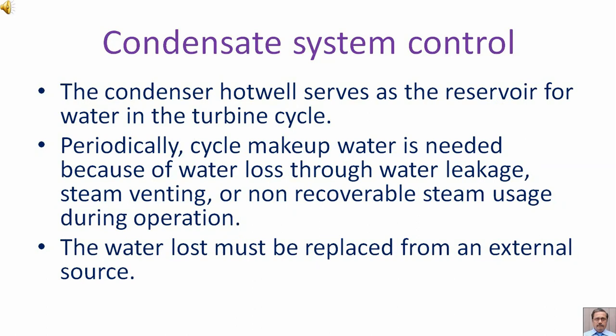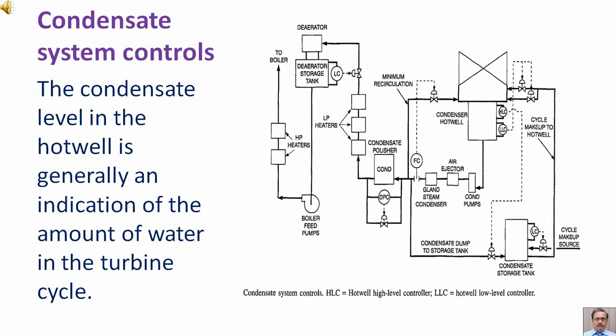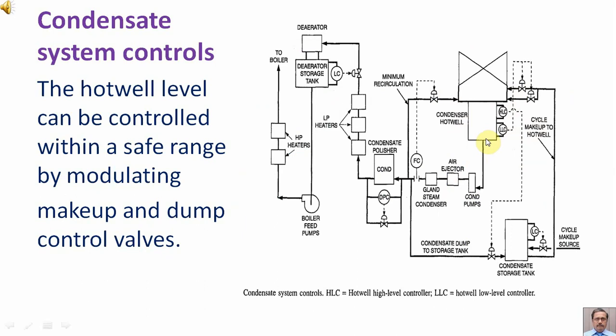The condenser hot well serves as the reservoir for water in the turbine cycle. Periodically, cycle make-up water is needed because of water loss through water leakage, steam venting, or non-recoverable steam usage during operation. The water loss must be replaced from an external source. The condensate level in the hot well is generally an indication of the amount of water in the turbine cycle.